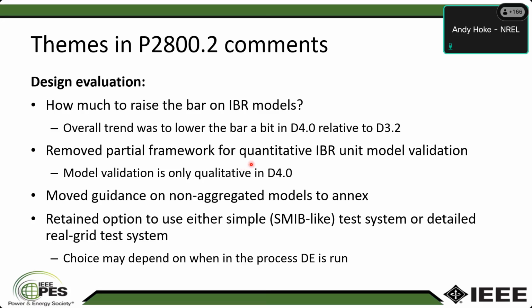That's actually not that huge of a shift because the quantitative framework was always kind of a suggestion and was never really fully complete, but it's not even in there at all anymore. So that's maybe a to-do list for other work. There was also some discussion of to what extent do we need to require or suggest the use of non-aggregated models that have, say, every inverter or turbine represented, or maybe every feeder at least represented inside of the plant. That content was moved to an annex, so it's sort of a little bit less of a high bar there in terms of how often non-aggregated models would be used.